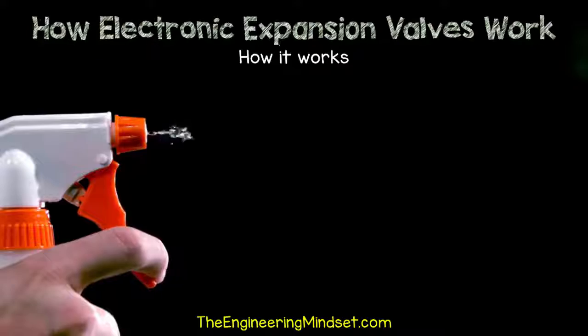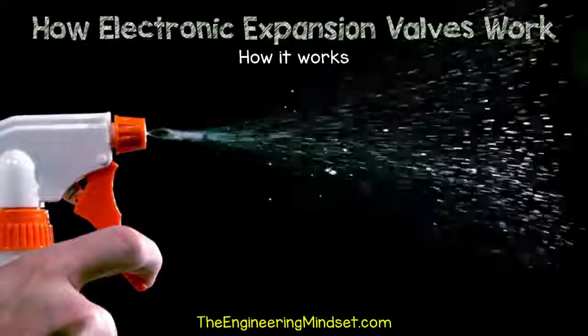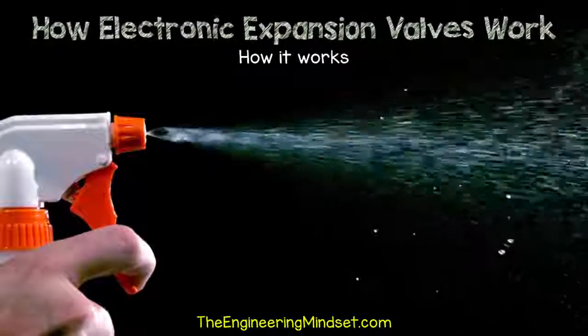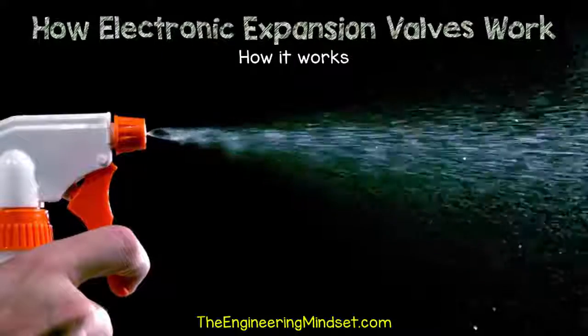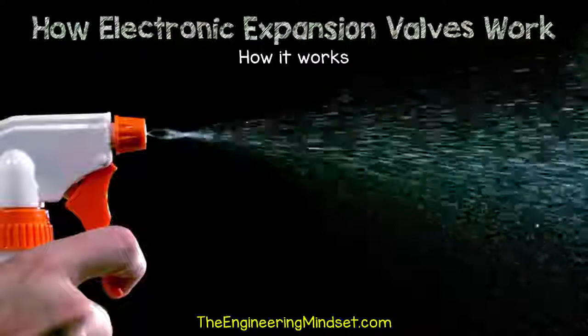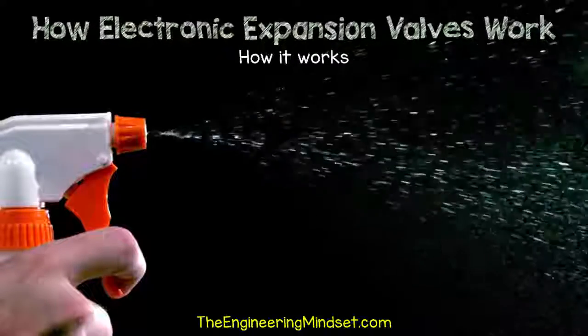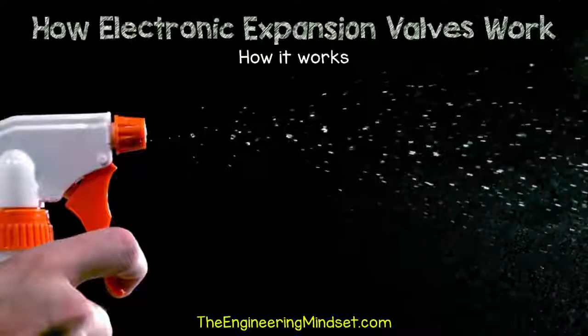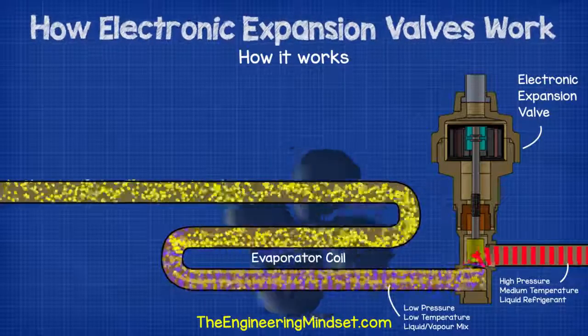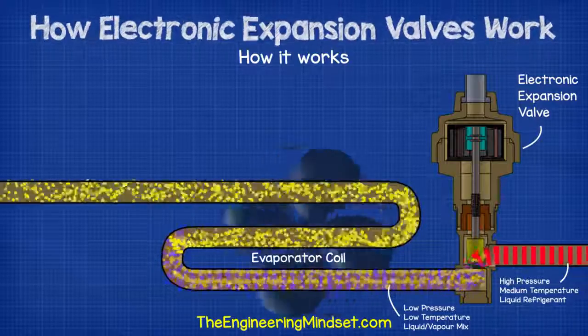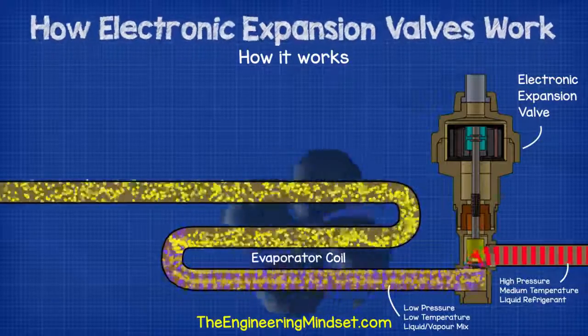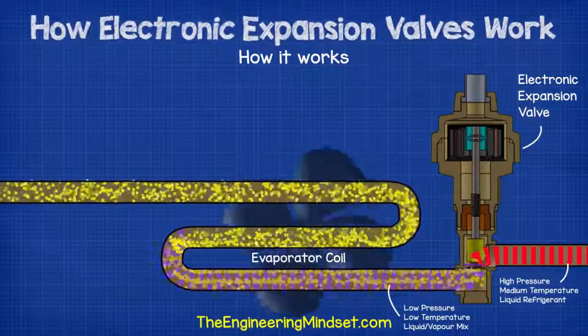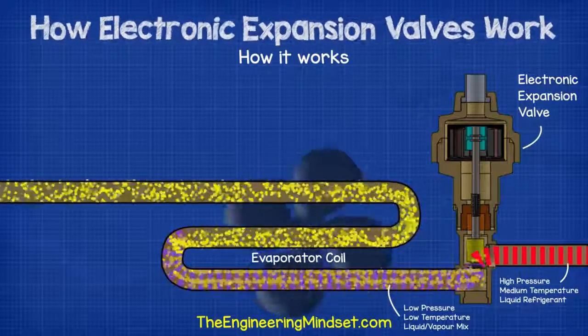If you want to visualize this, it's similar to a water bottle spray nozzle. As you pull the trigger, the high pressure liquid is forced through a small orifice into a much lower pressure atmosphere, which causes the water to become part liquid and part vapor. This mixture of liquid vapor refrigerant is sprayed into the evaporator where it will absorb heat from the air or water which surrounds the outside of the pipe which forms the evaporator coil.